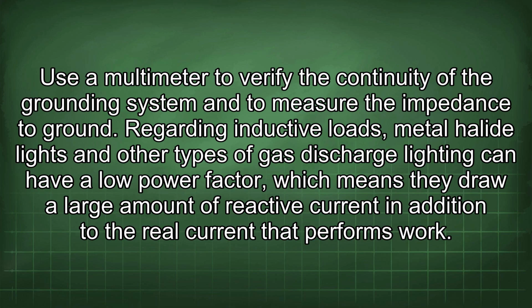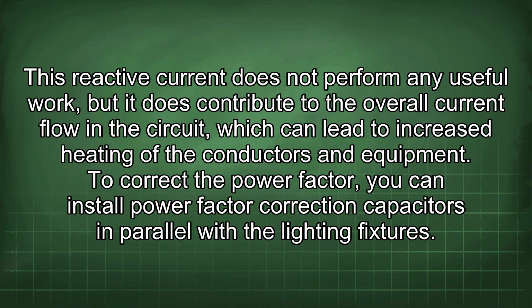Regarding inductive loads, metal halide lights and other types of gas discharge lighting can have a low power factor, which means they draw a large amount of reactive current in addition to the real current that performs work. This reactive current does not perform any useful work, but it does contribute to the overall current flow in the circuit, which can lead to increased heating of the conductors and equipment.